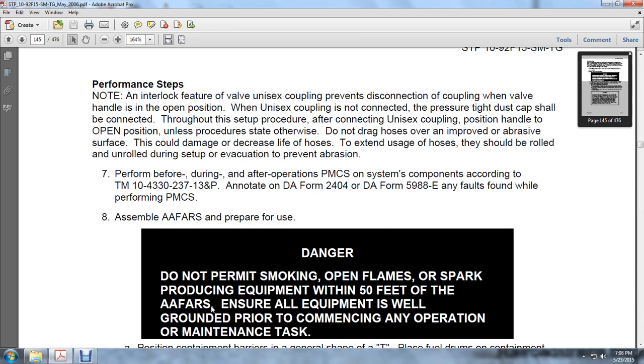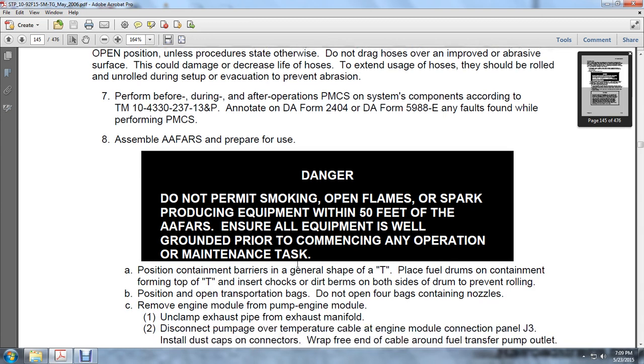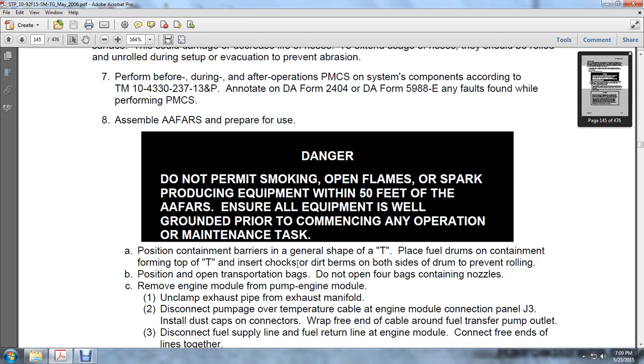Assemble the Advanced Aviation Forward Area Refueling System by preparing for use. Do not permit smoking, open flame, or spark-producing equipment within 50 feet of the AAFR system. Ensure all equipment is well grounded prior to commencing any operations or maintenance task. Position containment barriers in the general shape of a T. Place the fuel drums on the containment at the top of the T. Insert the chocks and berms on both sides of the drum to prevent rolling. Position open transportation bags. Do not open the 4 bags containing nozzles.